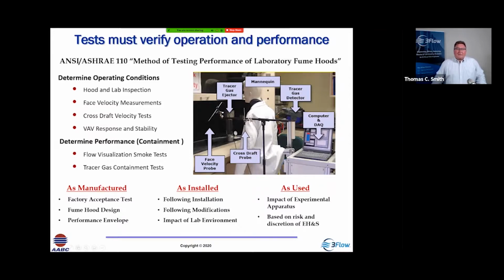So I think transitioning to IPA or some alternative as soon as possible is the best method. But think about how we ensure that the hoods function properly first. How do we get them to operate properly? If we can just do that, we will solve a lot of the problems. Use smoke tests in the interim to make sure that they contain properly. But if I was starting out today and was going to do this service today, I would say, let's focus on getting the hoods operating properly. Let's focus on getting the VAVs operating properly. Let's focus on getting the exhaust and the air handlers working properly. If the systems operate properly, they're likely to provide the right level of performance. So that's the biggest hurdle right there, getting everything to operate properly.